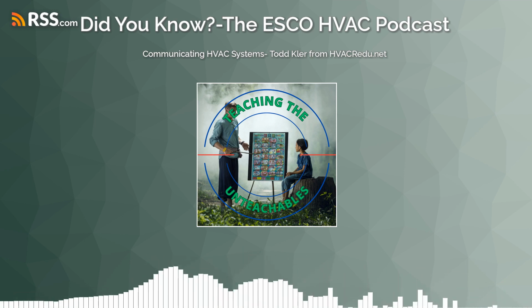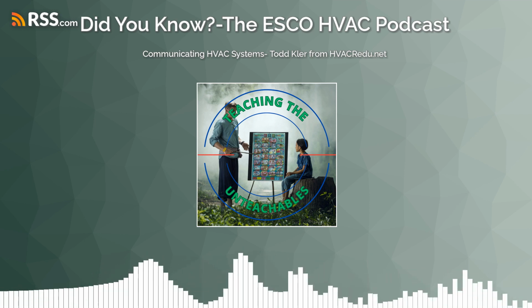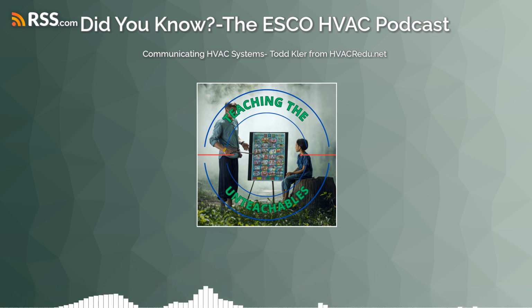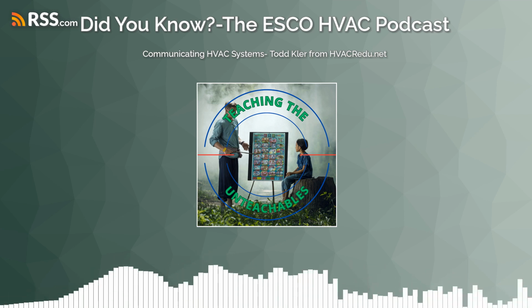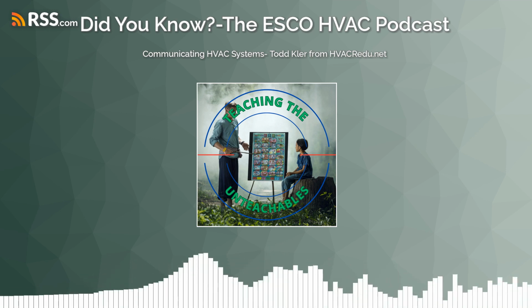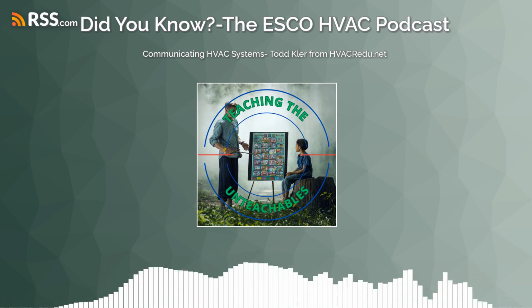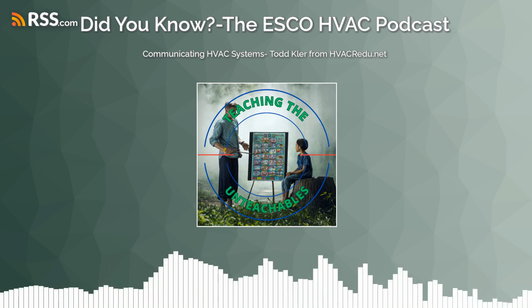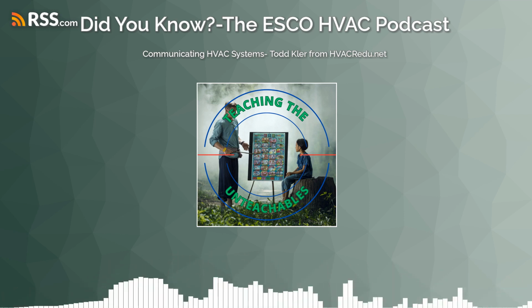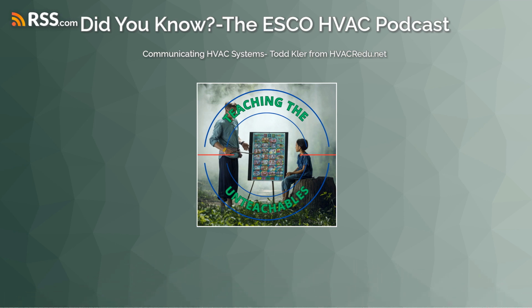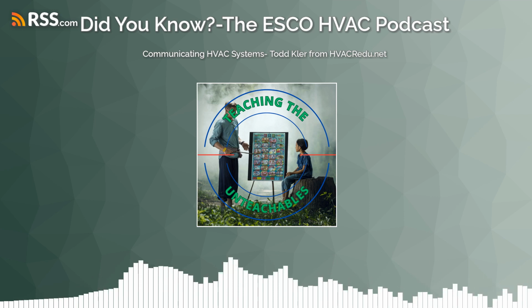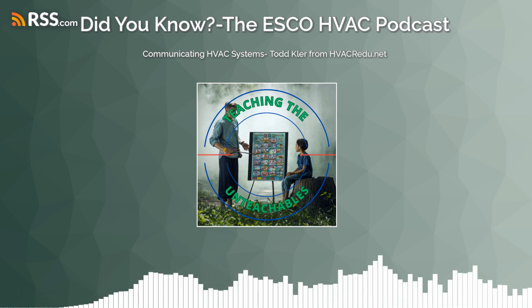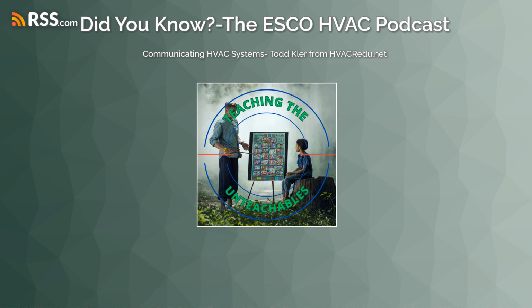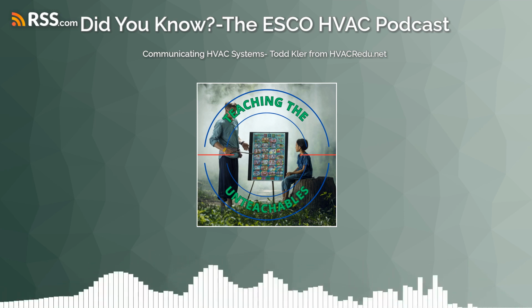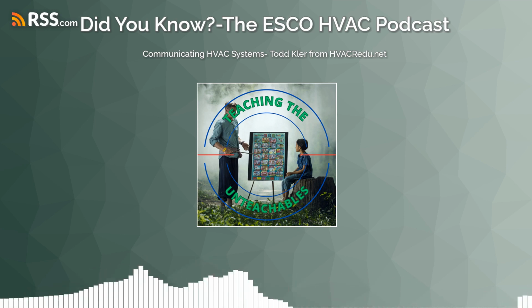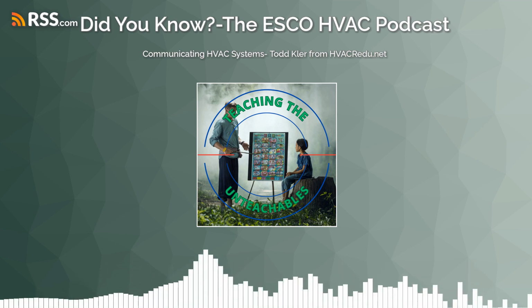So for those that are comfortable with the Daikin platform or the earlier Goodman Amana stuff that was using the ComfortNet platform, let's look at this real quick. Remember those 4 wires, yes, Todd? What we're going to use in this particular platform, we're actually going to use 2 of those for 24 volt AC. So that great big colorful screen that we have on our thermostat, right? We still need to light up. If we put batteries in it, we know what's going to happen. We had seen that back in the early 2000s when you put batteries in a digital thermostat, you burn them up. So we're actually going to use 2 of those for 24 volts AC, R and C, just like normal. And that common is actually very important.